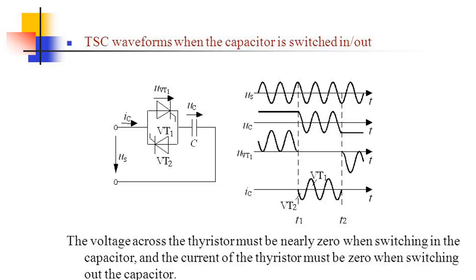TSC waveforms when the capacitor is switched in/out. The voltage across the thyristor must be nearly zero when switching in the capacitor, and the current of the thyristor must be zero when switching out the capacitor.